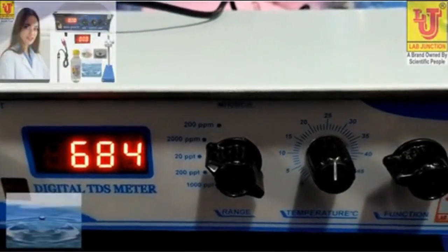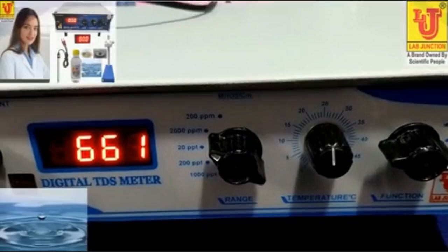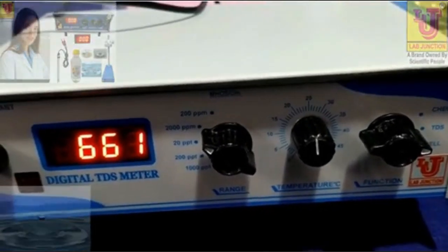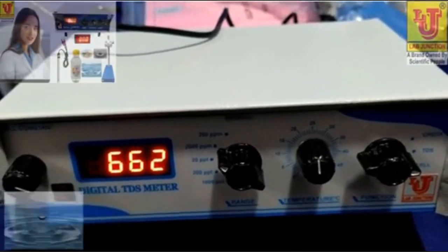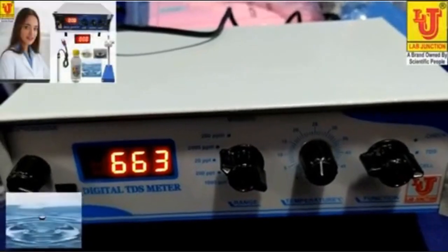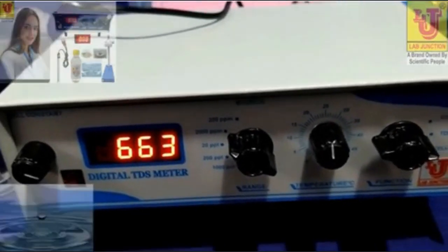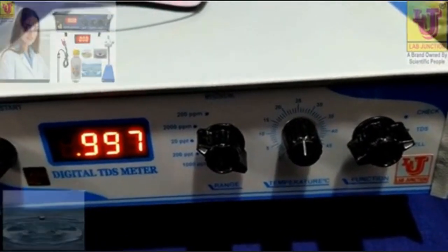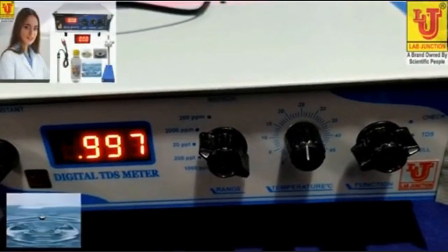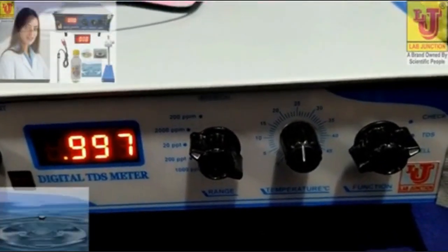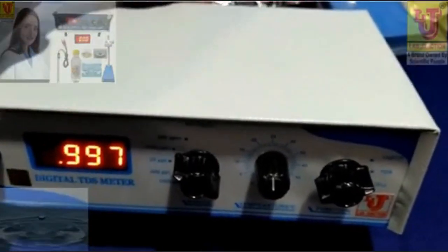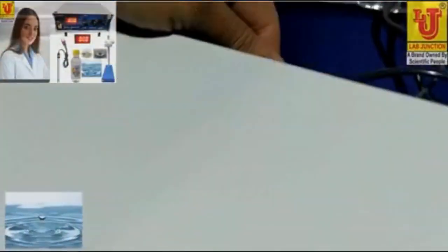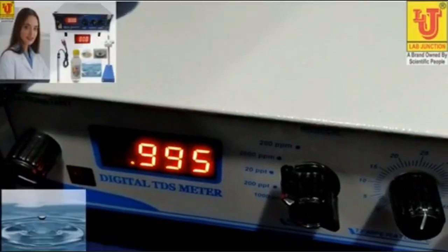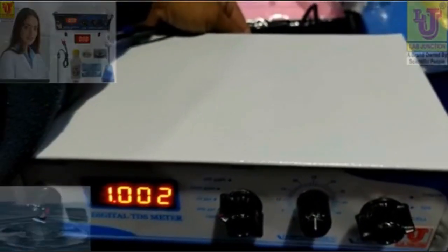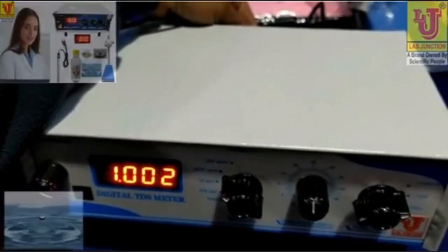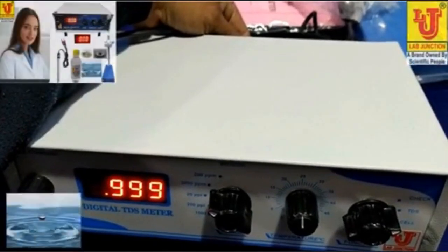Then some other person uses this digital TDS meter. After 1 week you come and need testing of digital TDS meter. Then you go to first check position. Check, this is 1.000. Suppose this is not 1.000, then you again set 1.000.